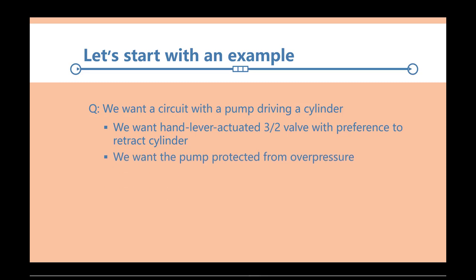We also want to protect the pump from overpressure, which is normal. If you have a fixed displacement pump pumping into a closed volume, you've got to do something. The pressure will rise very high if you don't have a relief path, and that could damage the pump or blow the seals out in the system. So can you draw this circuit? I'll pause here for a moment.